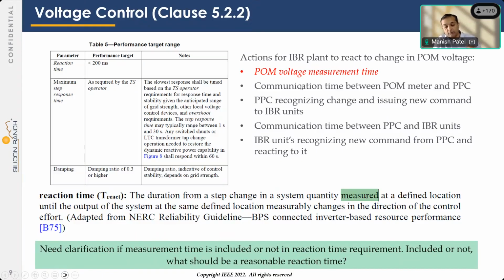There is a voltage at the point, there is a meter at the point of measurement that usually measures the voltage. It sends that voltage to the power plant controller, so there is a communication time between the meter and the PPC. When the PPC does get the new voltage from the meter, there is a little bit of time delay before it actually recognizes the change in the voltage, and then it issues a new command to IBR units. There is an extensive communication network between the PPC and all the IBR units in the plant, so there is some communication delay there. And then at the end, once IBR units get a new command from the PPC and react to it, there is a bit of time delay in there.